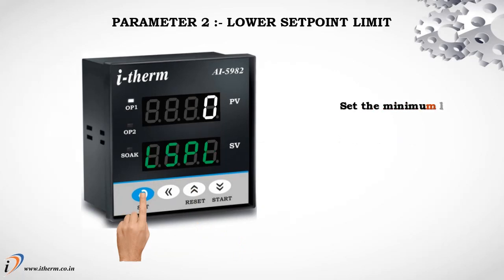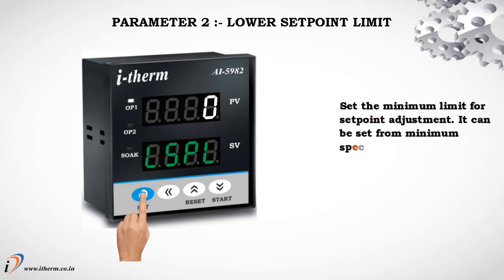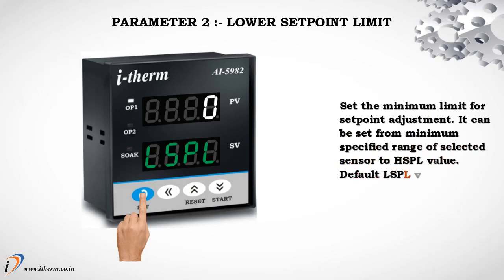Parameter 2: Lower Set Point Limit (LSPL). Set the minimum limit for set point adjustment. It can be set from the minimum specified range of the selected sensor to the HSPL value. Default LSPL value is 0.